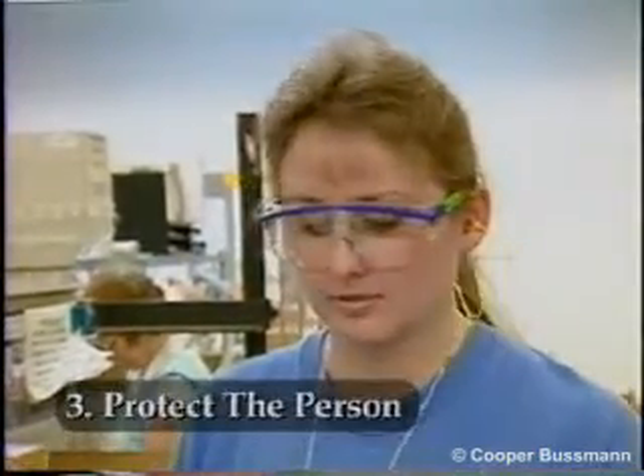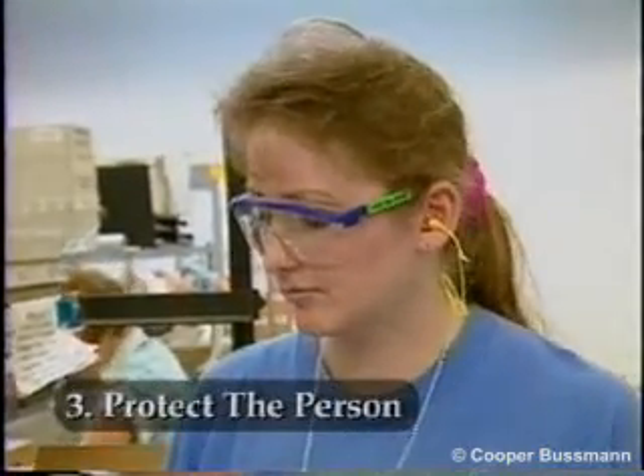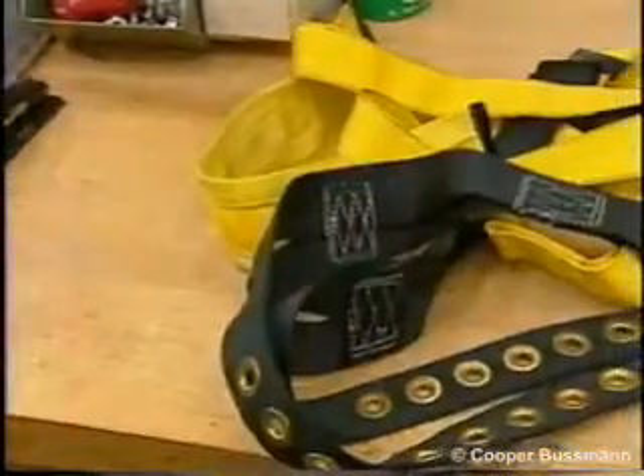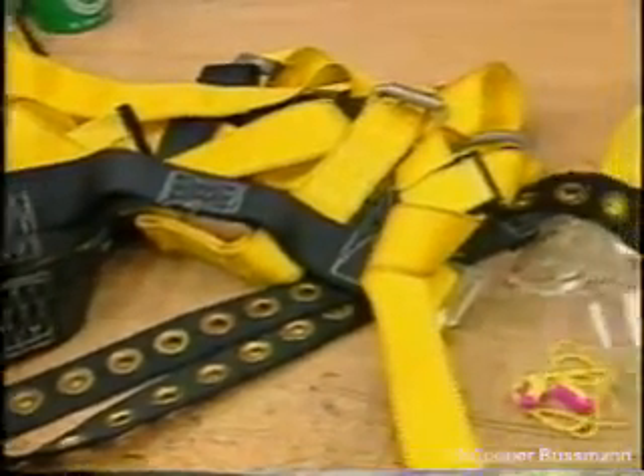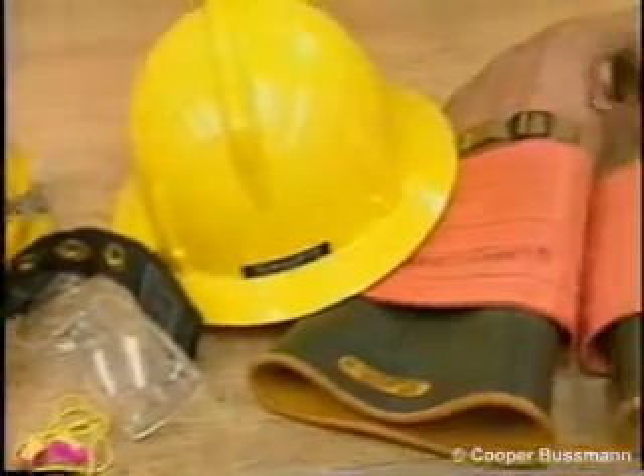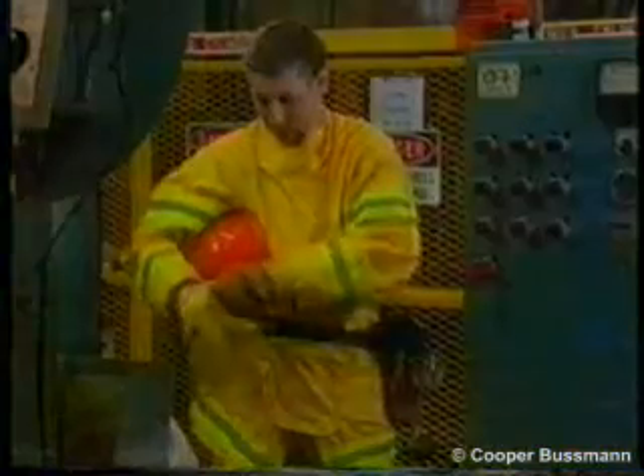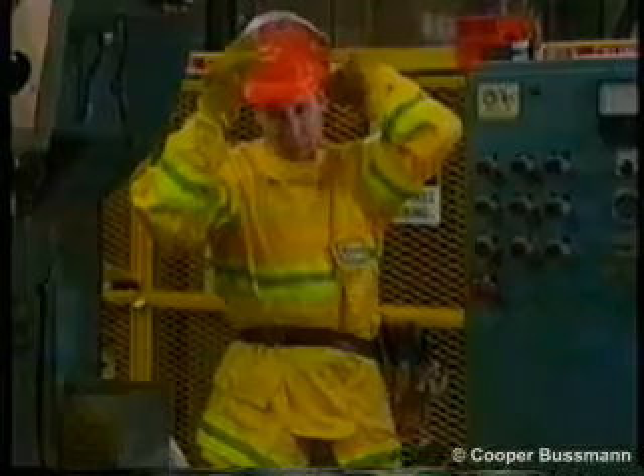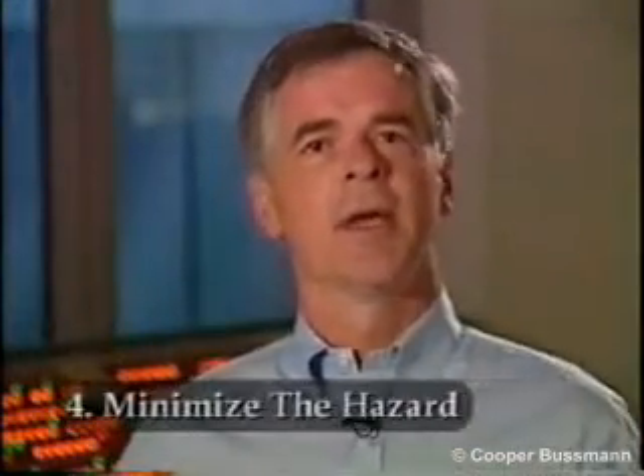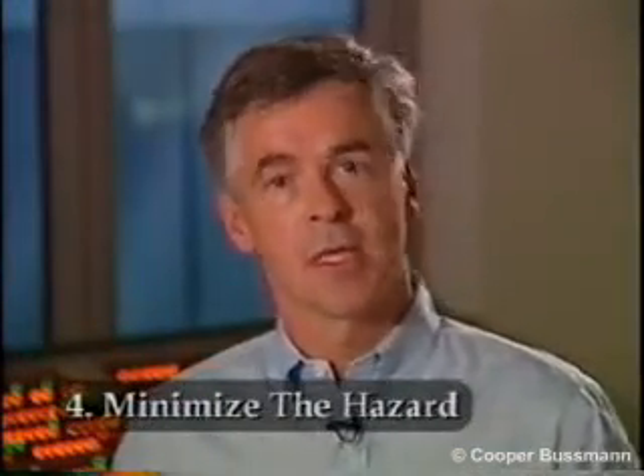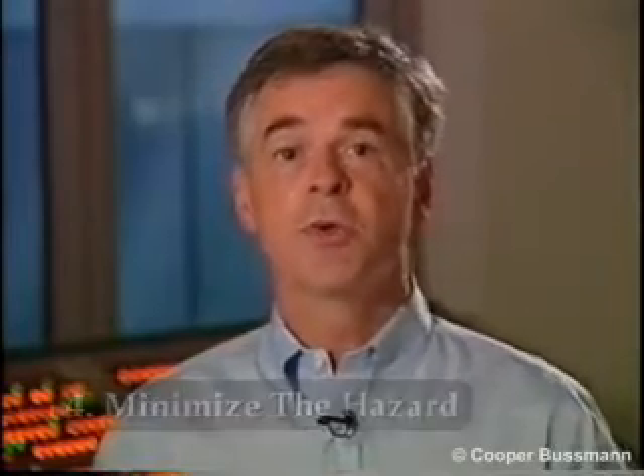Protect the person. Use the proper personal protective equipment for a job. This may include safety glasses or goggles, head protection, voltage-rated gloves, safety belt and harness, or flame-resistant clothing. Minimize the hazard. If it is impossible to establish an electrically safe work environment, be sure to shut down every possible energy source. Understand that sometimes a de-energized circuit can become re-energized, and do something to lessen the risk.